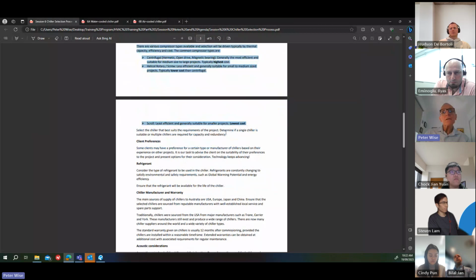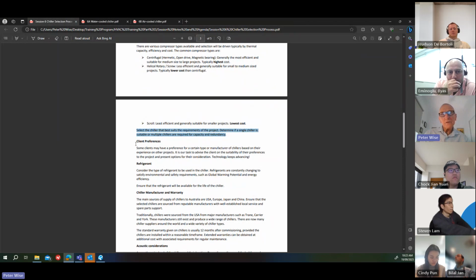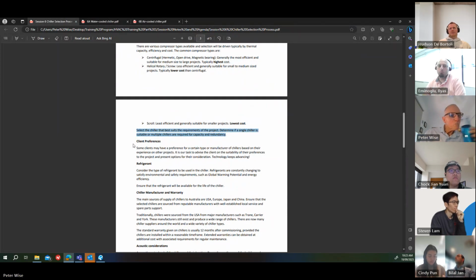So we need to select the chiller that best suits the requirements of the project. Determine if a single chiller is suitable, or you may need multiple chillers to achieve the capacity and redundancy. So redundancy is another factor to consider. If you've got a project that has to have cooling all the time, you can't afford to have a maintenance period or a shutdown or a breakdown. The chiller might fail. What happens if it does? You might need to have 2 chillers just to satisfy the redundancy requirement. Okay.